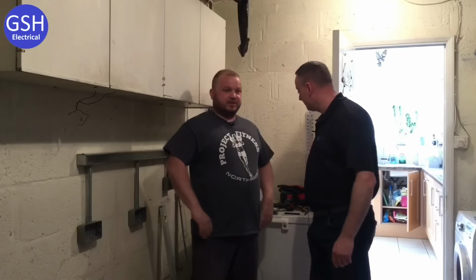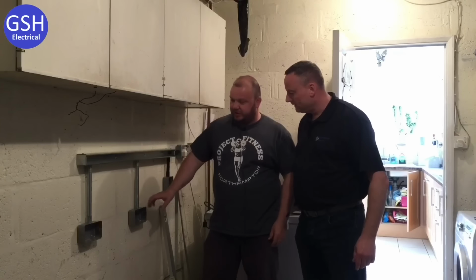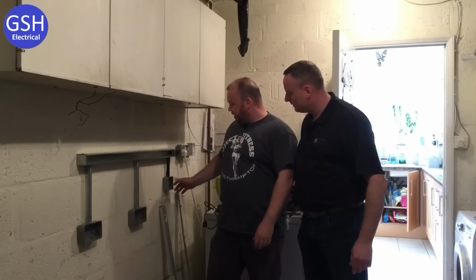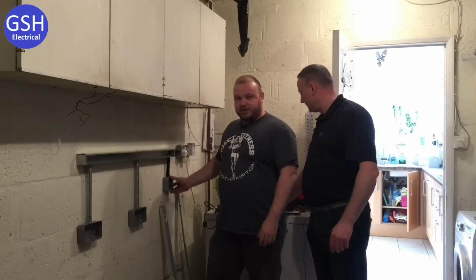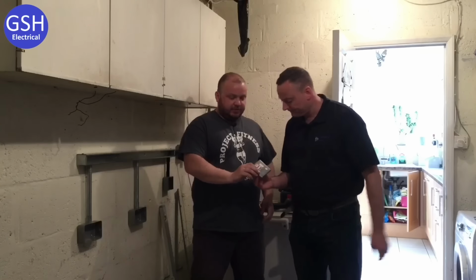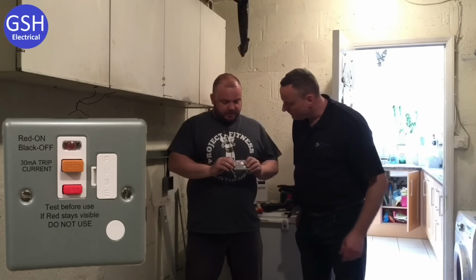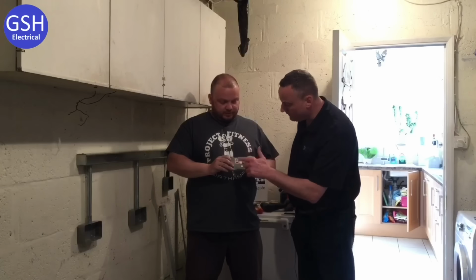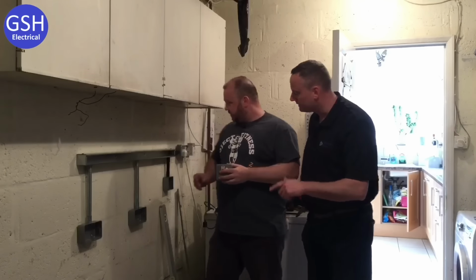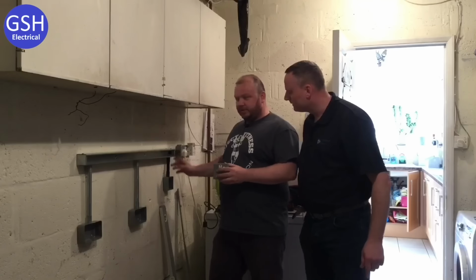So what are we doing today then, Mark? So we're putting in the steel trunking. We're adding 2 sockets. We've got to put in a fused spur unit, which is here, rated at 13 amps. It's got a 13 amp fuse in it. Why are we having to add an RCD onto these sockets? We're having to add an RCD into these sockets because the consumer unit isn't protected by an RCD.